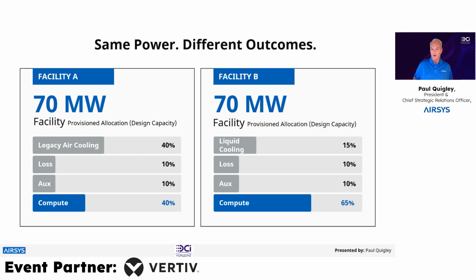If we move into an existing facility built with legacy air cooling, the most dominant type of cooling system for the last 20 years, we show that only 40% of the available provisioned power is provisioned for compute. It's important to stress the term provisioned, because legacy air cooling may only be occupying 10, 20, or 30% of the actual power, but 40% must be provisioned to it for peak loads, peak demand, inefficiencies, and things like that.